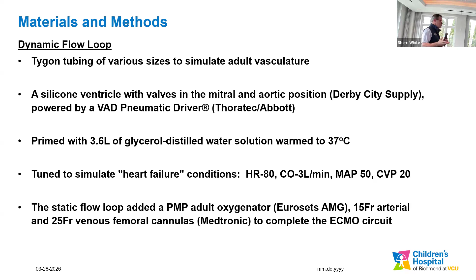This setup was primed again with that same glycerol distilled water solution to simulate some viscosity, warmed to 37 degrees Celsius, and then the VAD pump was tuned to sort of simulate heart failure conditions. So a heart rate of 80, a cardiac output of 3 liters per minute, mean arterial pressure of 50, and a central venous pressure of 20 millimeters of mercury. Then to the static flow loop model, they added a Eurosets adult ECMO oxygenator, a Medtronic 15 French arterial and 25 French femoral venous cannulas, and that completed the ECMO portion of the circuit.